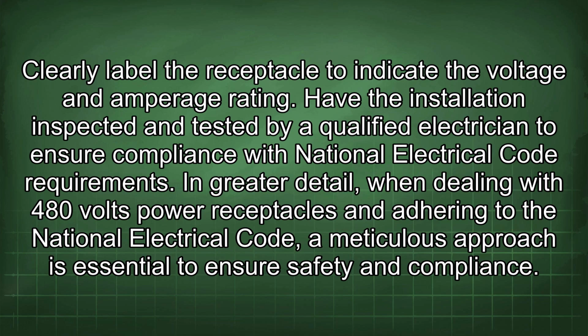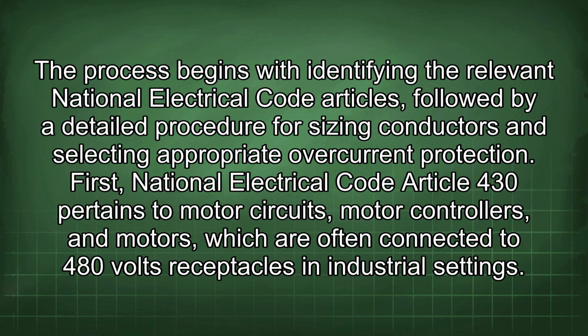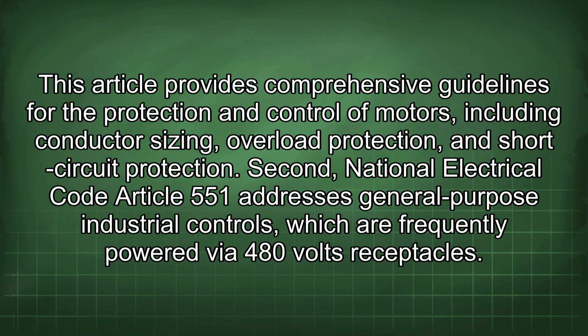In greater detail, when dealing with 480 volts power receptacles and adhering to the National Electrical Code, a meticulous approach is essential to ensure safety and compliance. The process begins with identifying the relevant National Electrical Code articles, followed by a detailed procedure for sizing conductors and selecting appropriate overcurrent protection. First, National Electrical Code Article 430 pertains to motor circuits, motor controllers, and motors, which are often connected to 480 volts receptacles in industrial settings. This article provides comprehensive guidelines for the protection and control of motors, including conductor sizing, overload protection, and short-circuit protection.